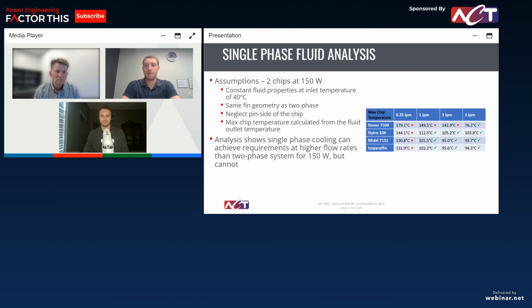So oftentimes, a cold plate is what we'll use, especially if we're direct cooling power electronics. Like you have a circuit board with a bunch of power electronics on it, we'll design a cold plate that acts as the evaporator, and it'll have internal channels where your fluid flows, collects the heat from those power electronics, and then boils and vaporizes and moves on to your condenser. So sometimes in certain applications they're interchangeable. Evaporator, I would say, is the broader term, because sometimes evaporators are not cold plates, but in most two-phase systems, a cold plate will be an evaporator.